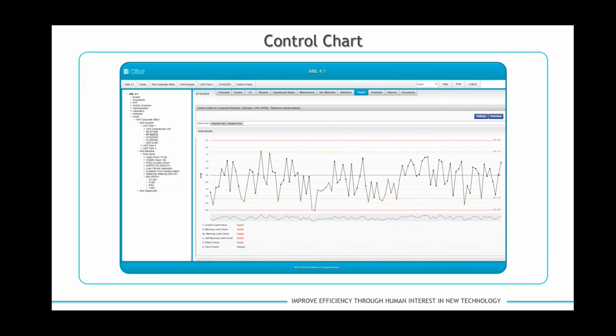You just do your work in the field, and at the end of the day you spend 30 minutes to an hour going into the system to check all the instruments you've been validating that day. You go through the control charts and check if your instrument is still running correctly. I saw at the instrument that my validation was within its limits, but is it trending, or do I have an offset problem, for example? It can help make your work much more efficient and better quality as well.